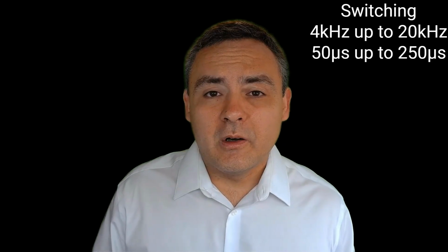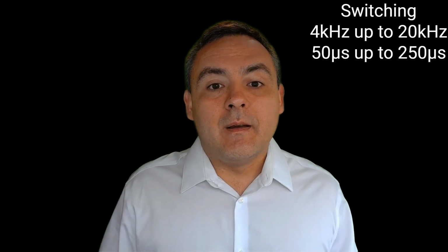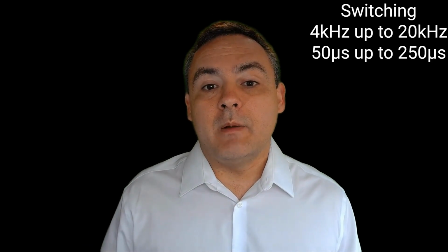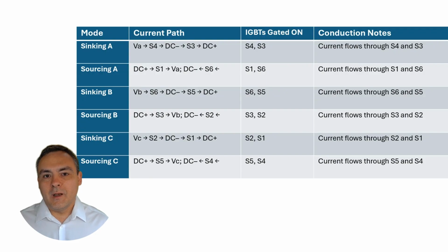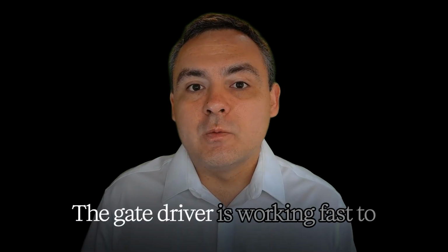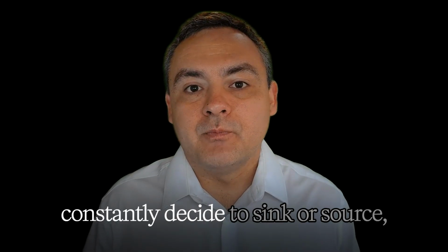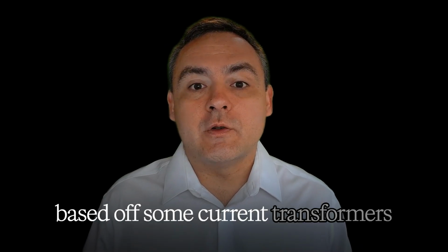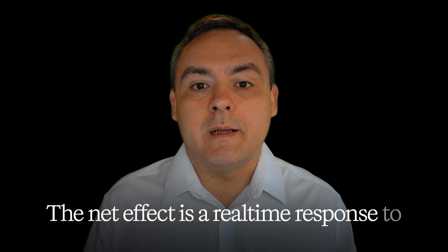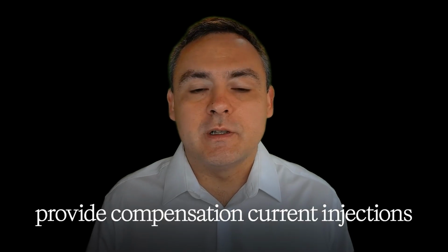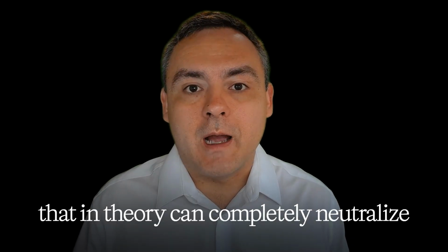These switches happen extremely fast. I'm talking about 4 kilohertz up to 20 kilohertz. That's 50 microseconds up to 250 microseconds. Fast, right? You can have these combinations of switching. The gate driver is working fast to constantly decide to sink or source based off some current transformers and voltage-sensitive devices placed where you want to mitigate harmonics.